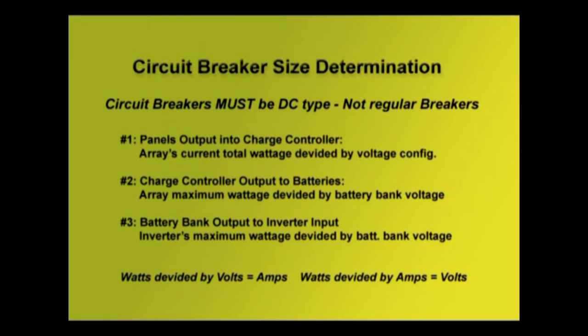What we're doing here, take a look. We're using the old formula, watts, volts, and amps. If you divide watts by either volts or amps, you get the other one. So watts divided by volts equals amps, and watts divided by amps equals volts. Whichever one you don't know, it gets that one for you. Now, breakers don't come in every size imaginable, so take the number you come out with and round it up to the next size breaker that is available.